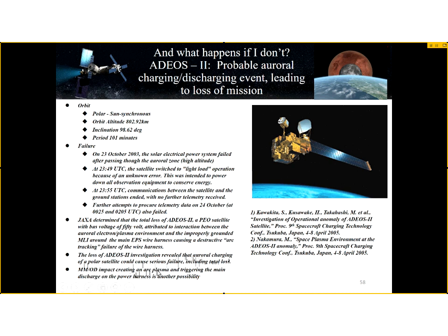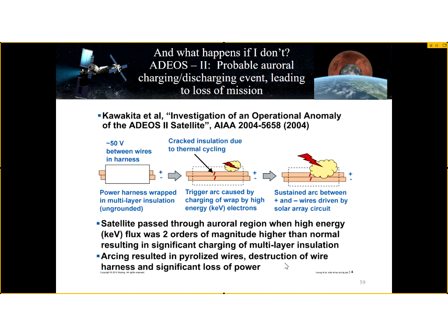MMOD impact could have done that too, but there's more to this story in that those 50-volt wires, which were carrying many amps, were insulated with Tefzel, which was real popular at the time because everybody was upset about Kapton arc tracking. Well, this Tefzel in this configuration was running 20 to 30 degrees centigrade over its maximum recommended use temperature. Its additive package was outgassing away, and it was becoming brittle.